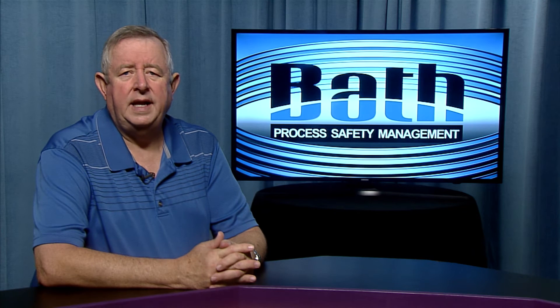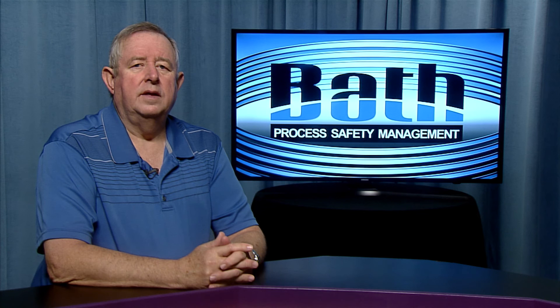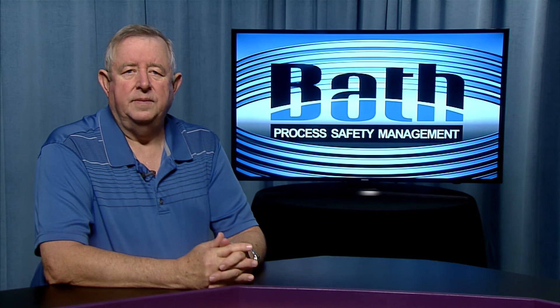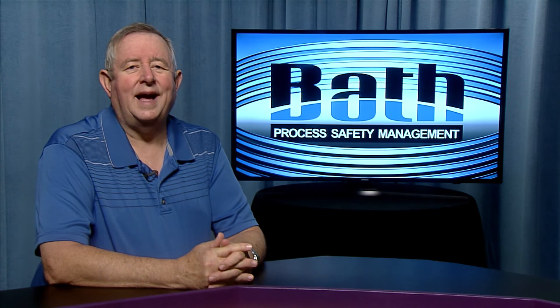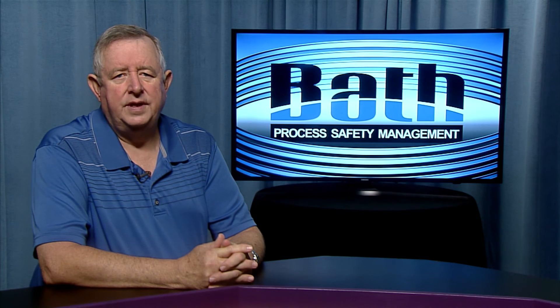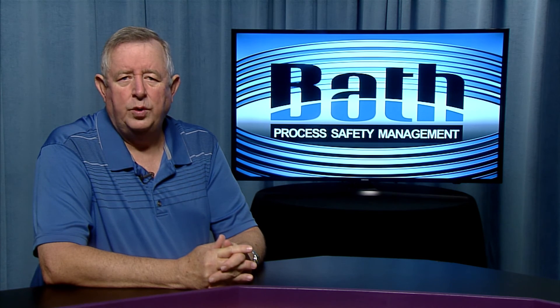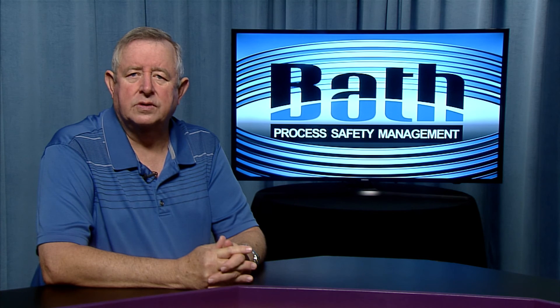The purpose of API-RP500, as stated in Section 1.1.1 under the heading Purpose, and I quote: is to provide guidelines for classifying locations Class 1, Division 1 and Class 1, Division 2 at petroleum facilities for the selection and installation of electrical equipment. The overall goal for both of these documents is for the end user to assign a proper classification to the location under consideration, allowing the proper installation of electrical and electronic equipment and wiring methods which meets the requirements of the National Electrical Code.